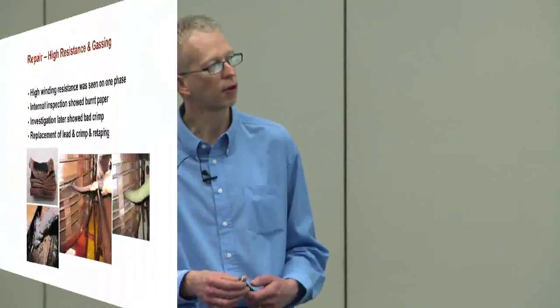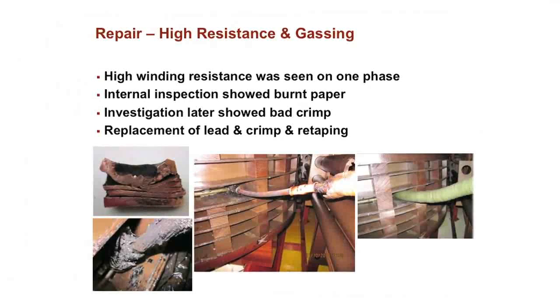Other typical things are adding barriers between windings or around leads, modifying the clamping system, or securing leads better. So you can do a lot inside a transformer without taking it to a repair factory. And this is just another example of a transformer. This is the one that had a very high winding resistance, and you could also see something in the DGA.